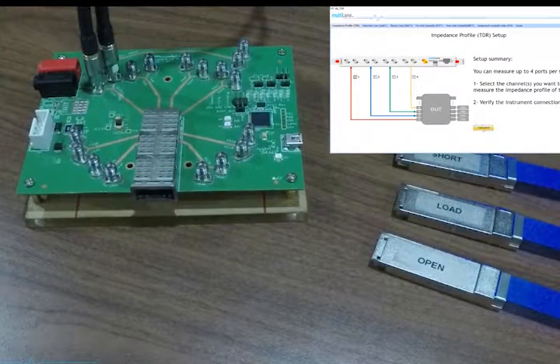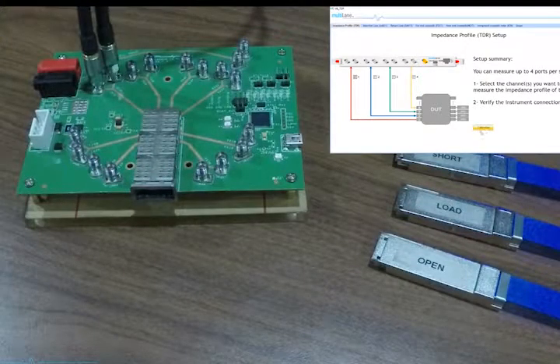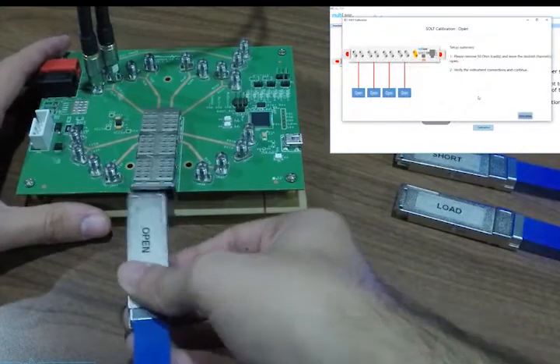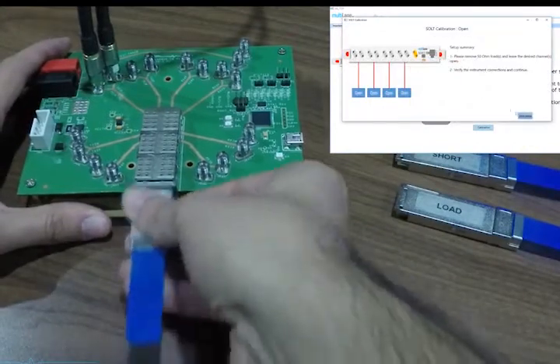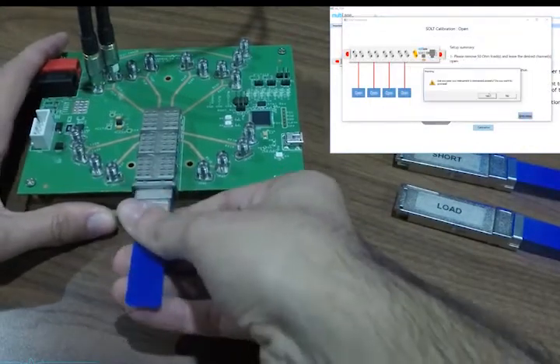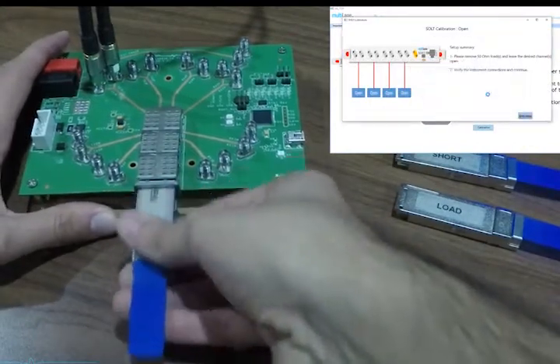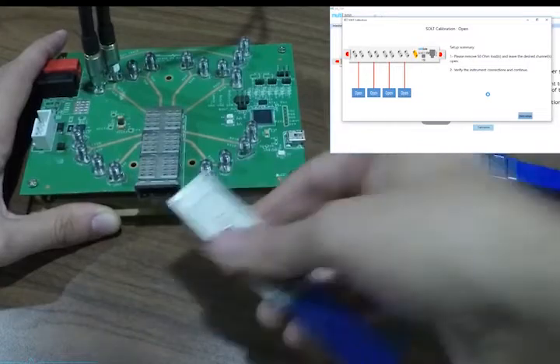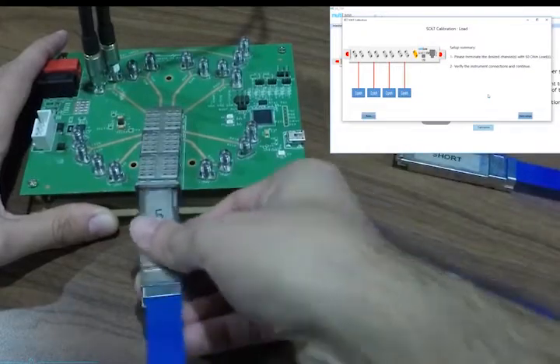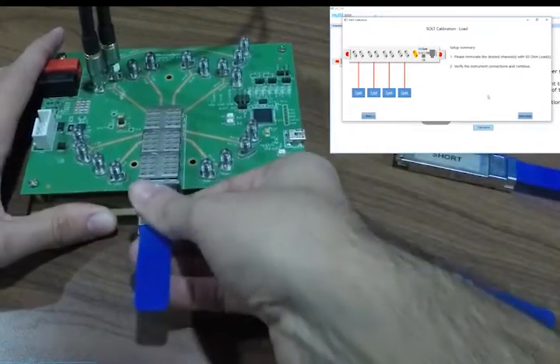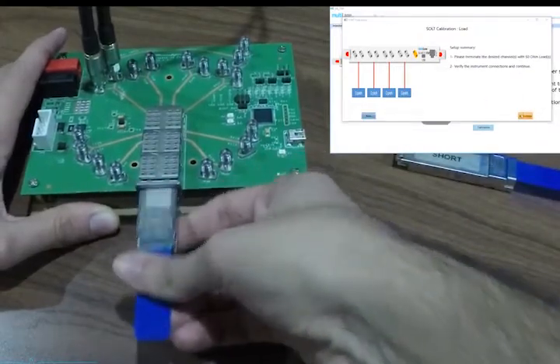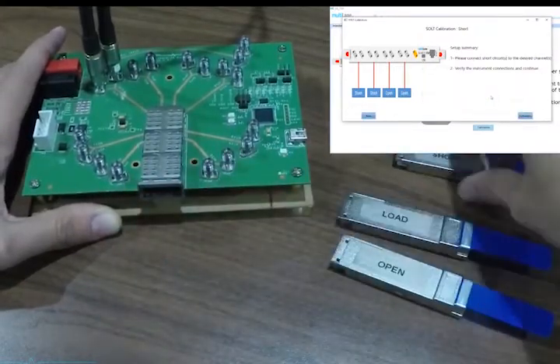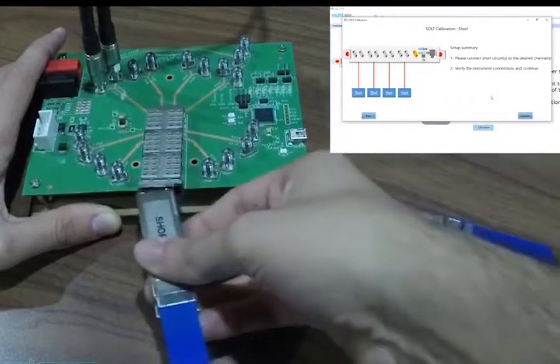SOLT calibration is performed for TDR measurement using the provided open, short and load QSFP calibration modules. Reference measurements are taken for each of the three modules successively as instructed on the ML4025TDR software.